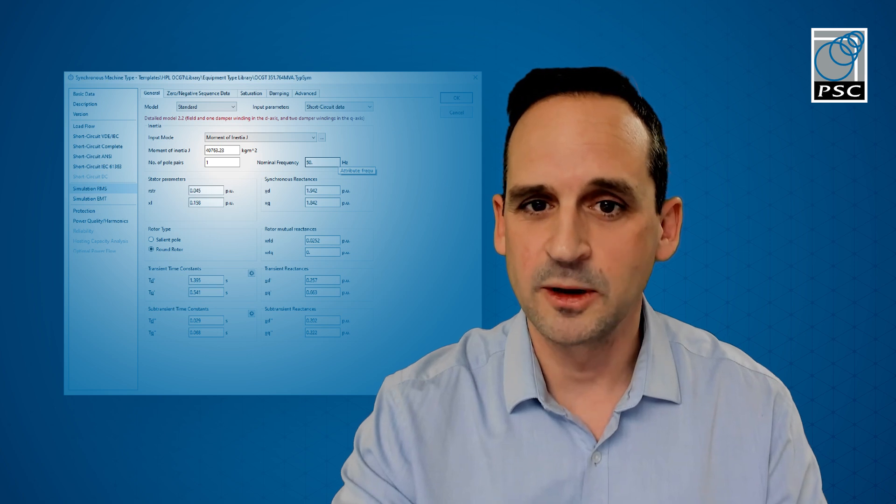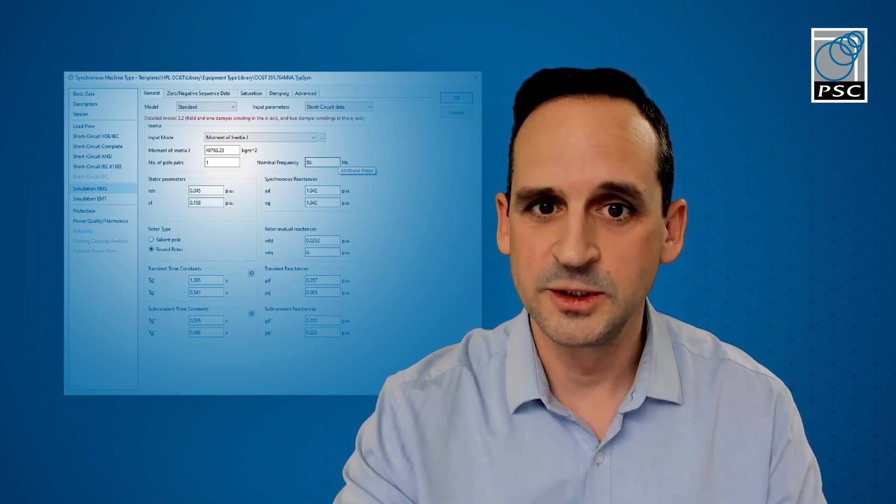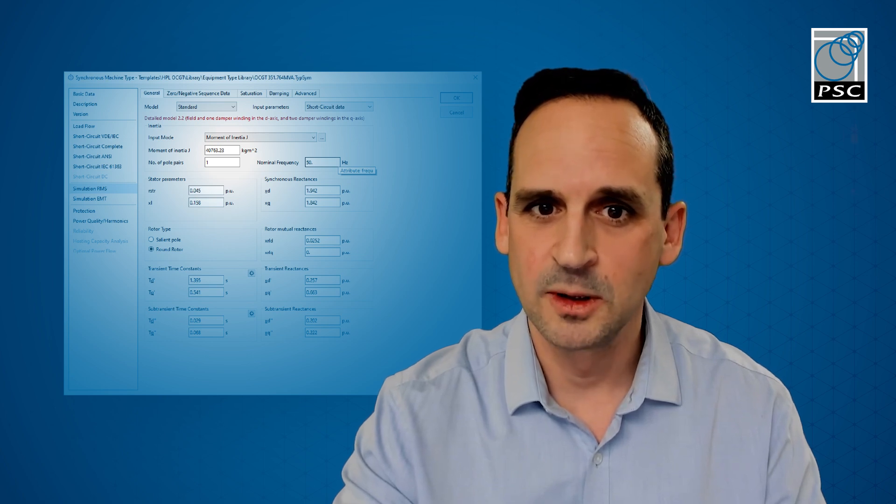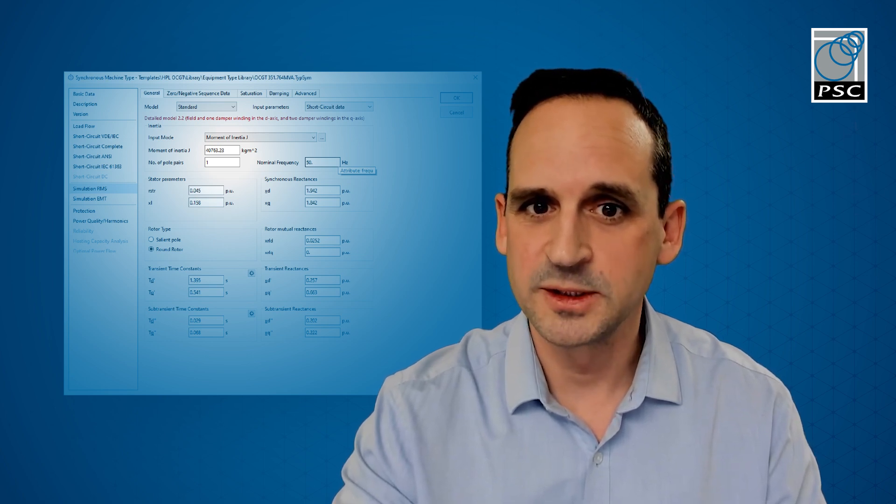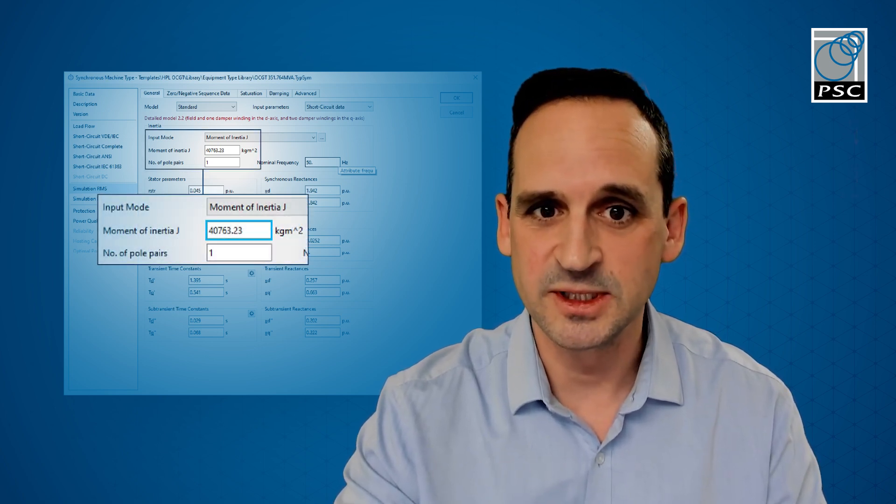This screen represents a lot of the physical electrical characteristics of the machine, which should be provided in the manufacturer's data. Of particular importance for a dynamic study such as fault ride-through is the rotor inertia, as this affects the machine's resistance to acceleration.